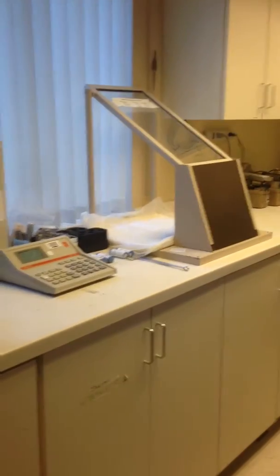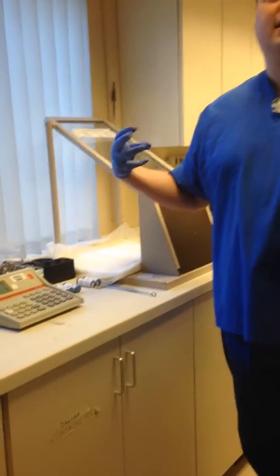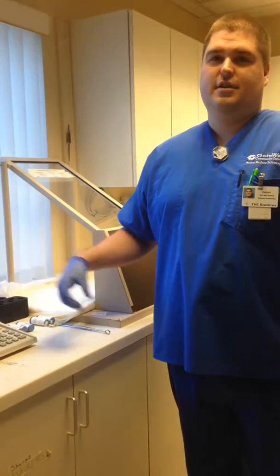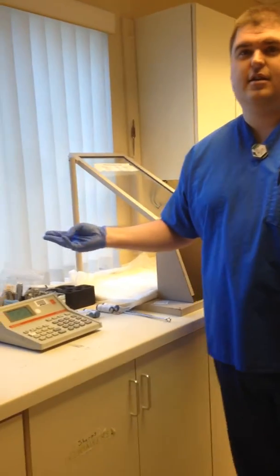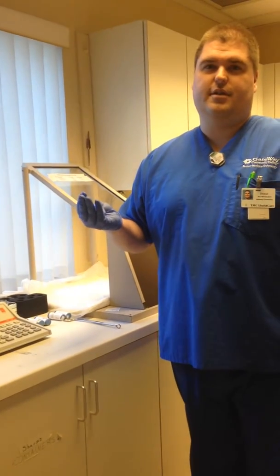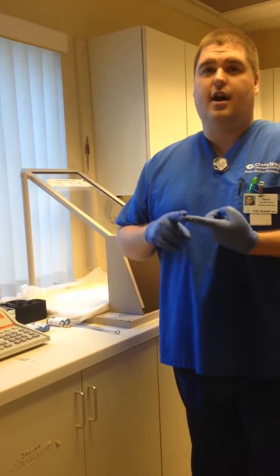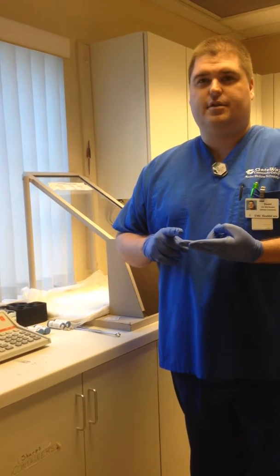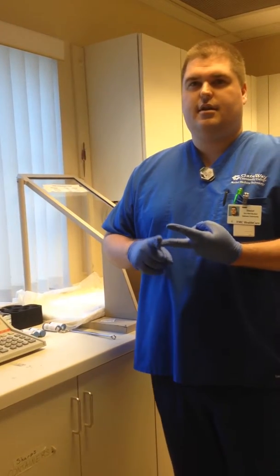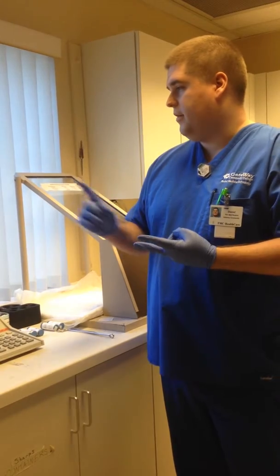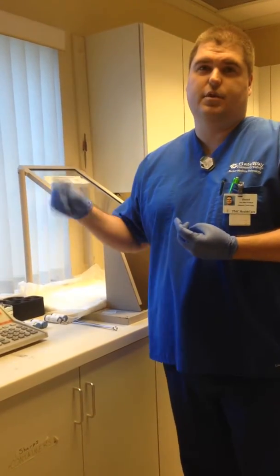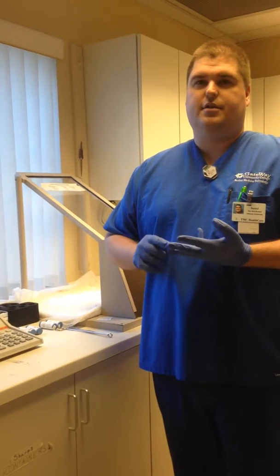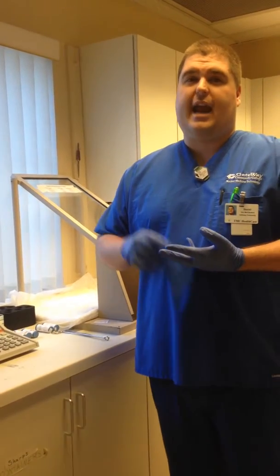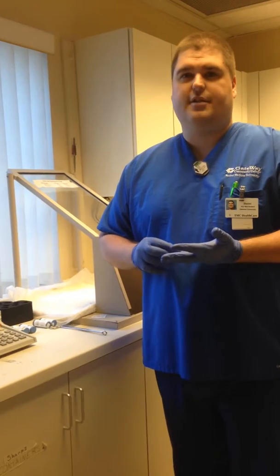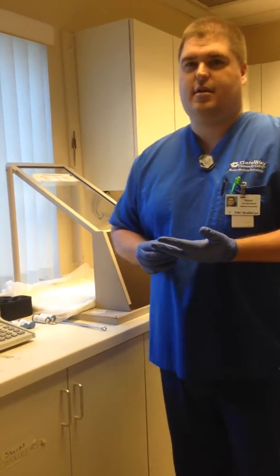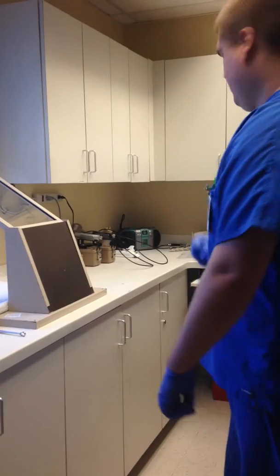Okay, and what is this quality control? This is the constancy quality control. So with the dose calibrator, there's four types of quality control that we do. Daily we do the constancy, and then we also do geometry, which we do whenever the dose calibrator is installed, moved, or repaired. And then we also do accuracy, which is done annually. And then we also do linearity, which is done quarterly, okay? So today we're doing the constancy.